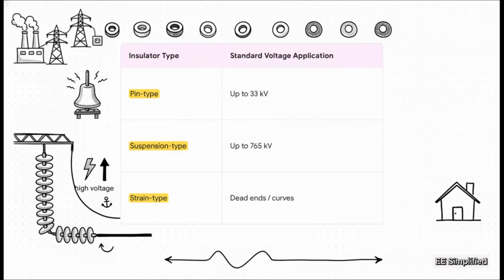Now, for the overhead lines, the real unsung heroes are the insulators. You've definitely seen them, those stacks of ceramic or glass discs hanging off the arms of the towers. Their only job is to stop that high-voltage electricity from taking a disastrous shortcut down the metal tower to the ground. The type they use tells you a lot about the voltage. Little pin-type ones are for lower voltages, but for our high-voltage highway, you need long, dangling strings of suspension-type insulators to handle that incredible electrical pressure.